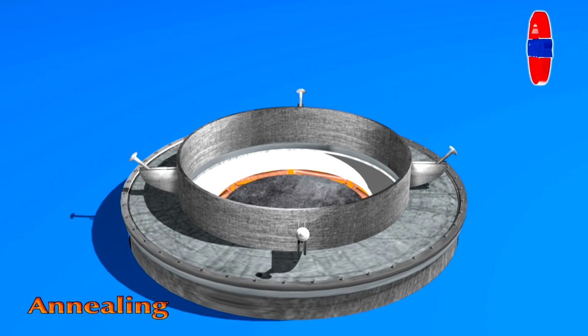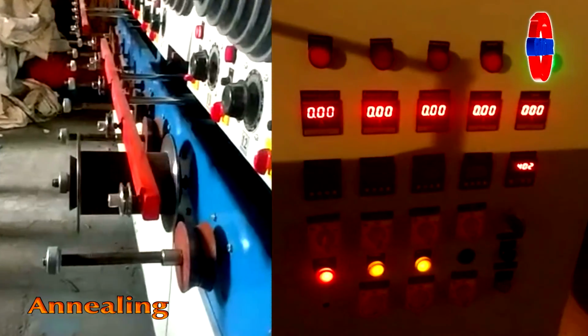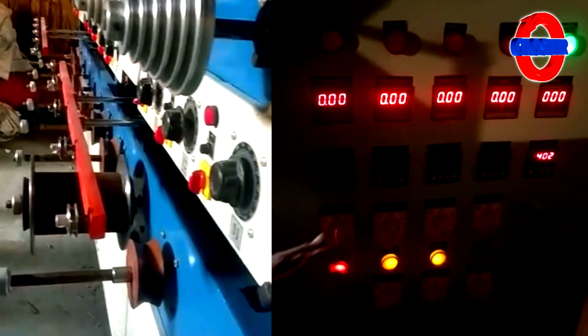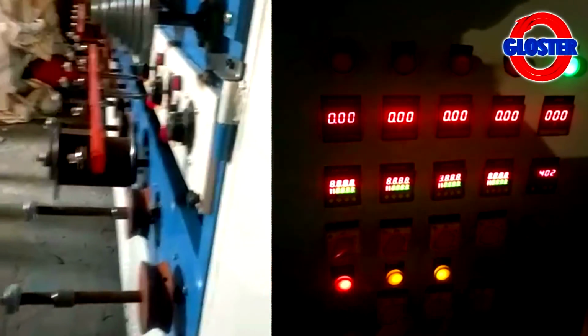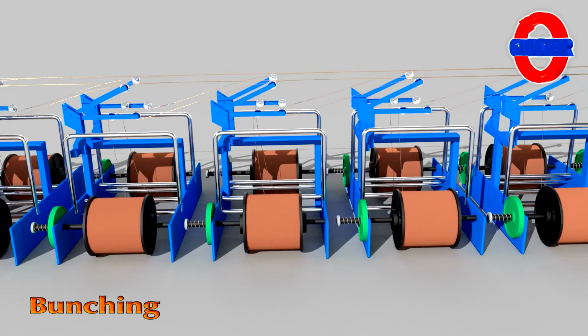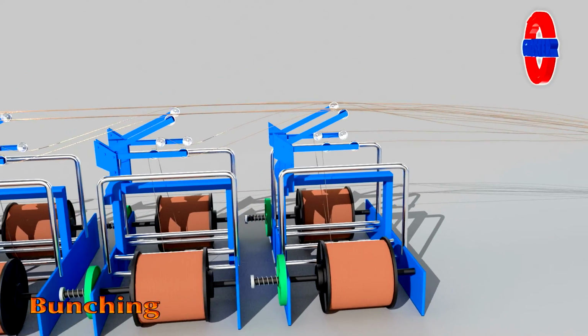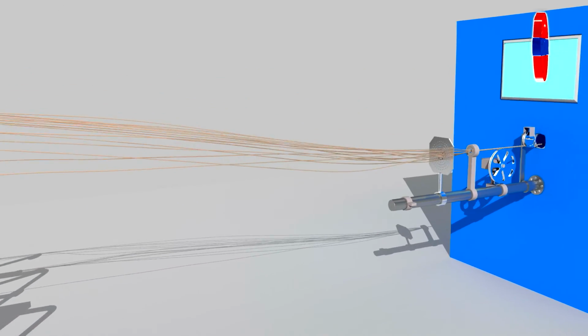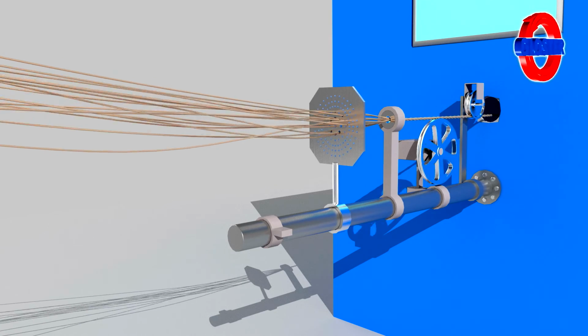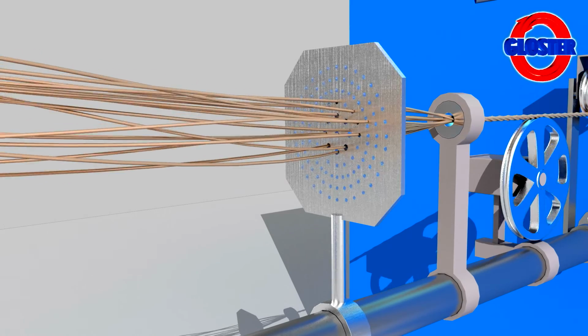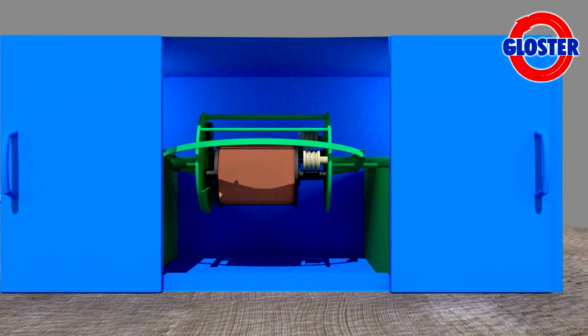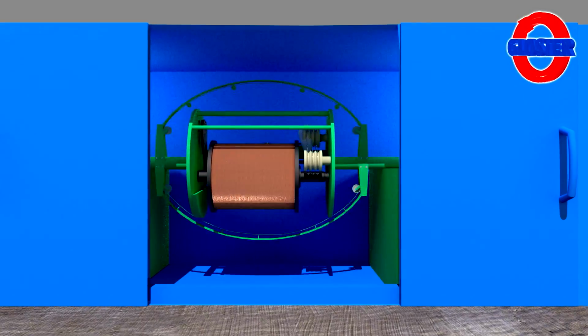Next process is annealing the drawn copper wire to reduce hardness, stress and eliminate chances of wire breakages during use. Further is bunching process, which includes required number of wires as per relevant IS standards. These wires together are twisted in the bunching machine at pre-decided twists per meter and then wound out in metallic bobbins.